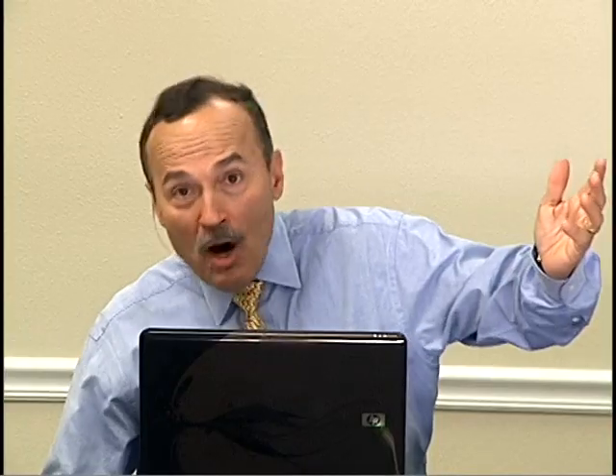Okay, red indicates stop. And when you press the button, the light goes off, which indicates either the motor's running, or the bulb is burnt out, or power failure. Oh, power failure. There you go. Hey, is the motor running? Yep. Well, how come we got no power in the building? Well, the bulb's out. Motor must be running. Isn't it right? I'm not quite sure if that's the best design to indicate whether the motor is running or not, but whatever. We'll go with what we got here.